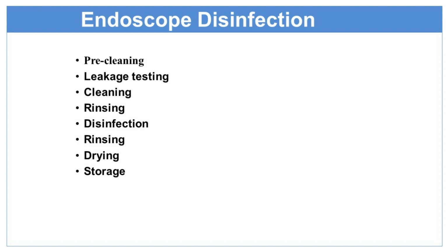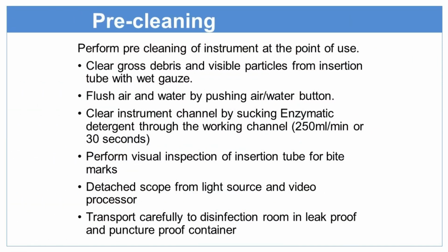The sequence is like this: pre-cleaning. Soon after the procedure finishes, we should wipe the scope externally, or clean the surface of the scope. Then after pre-cleaning, a leakage test should be done. Then cleaning, again cleaning, then rinsing, disinfection, and then again rinsing, drying and storage. We will also see where we are going to store the endoscope and how we will place it. So in pre-cleaning, perform pre-cleaning of instruments at the point of use.